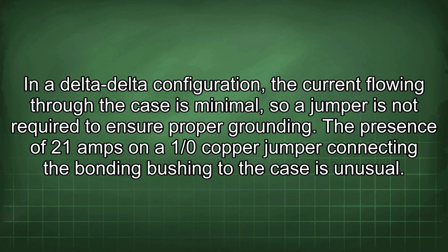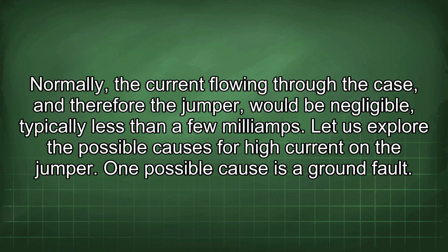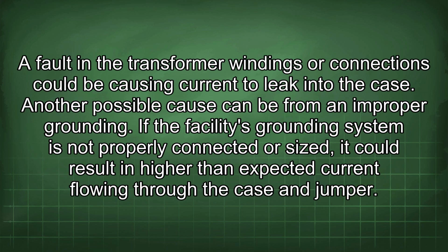proper grounding. The presence of 21 amps on a 1/0 copper jumper connecting the bonding bushing to the case is unusual. Normally, the current flowing through the case, and therefore the jumper, would be negligible, typically less than a few milliamps. Let us explore the possible causes for high current on the jumper. One possible cause is a ground fault. A fault in the transformer windings or connections could be causing current to leak into the case.